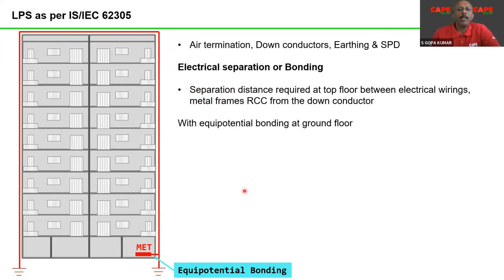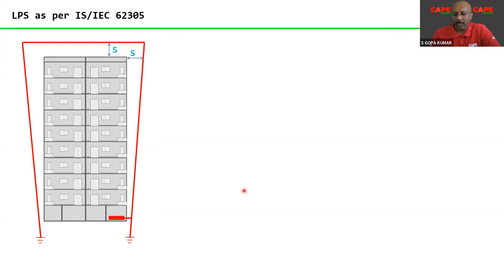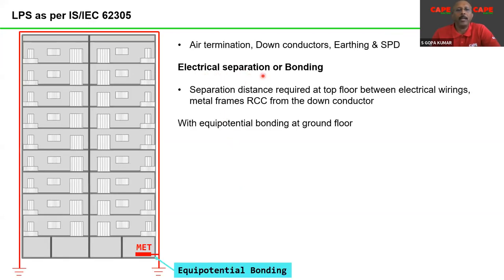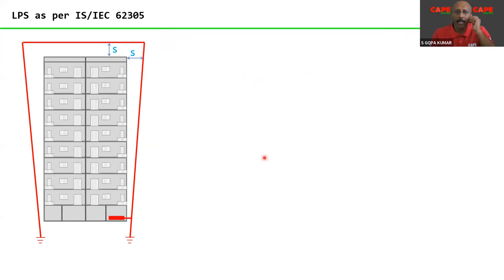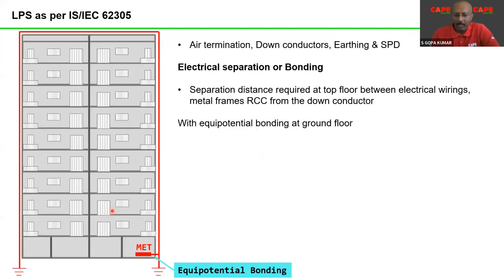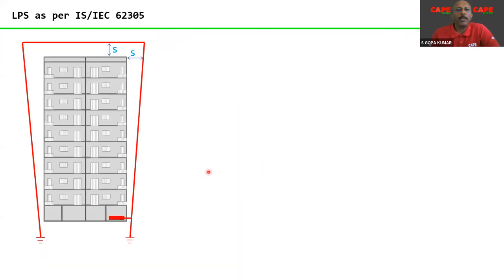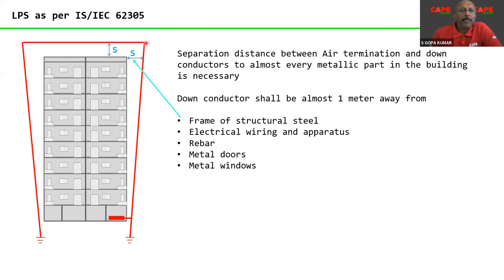Now, how to calculate the electrical separation distance? As I said here, there are two techniques. One is electrical separation, the next one is bonding, which means you make equipotential bonding everywhere. First, let us look at what electrical separation is. Electrical separation means at the roof you have the air termination, then you have the down conductor, and at the bottom of the building you have the equipotential bonding. The parts of air termination mean the air terminal, the grid at the top, and the down conductor.